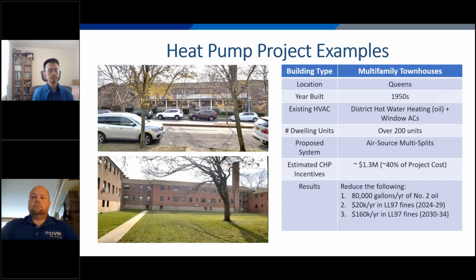The number of dwelling units is well over 200. Our proposed system, kept very simple, is air source, cold climate multi-split systems, designing one condenser per apartment. A typical apartment is about 500 to 700 square feet, so we size it at around 1.5 to 2 tons per dwelling unit.